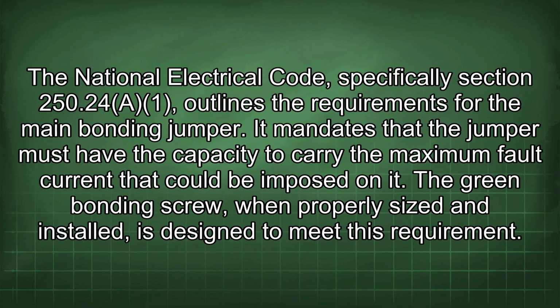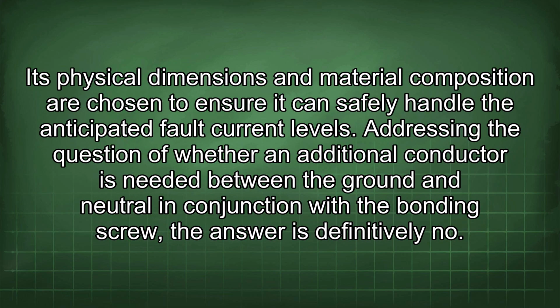The National Electrical Code, specifically Section 250.24(A)(1), outlines the requirements for the main bonding jumper. It mandates that the jumper must have the capacity to carry the maximum fault current that could be imposed on it. The green bonding screw, when properly sized and installed, is designed to meet this requirement. Its physical dimensions and material composition are chosen to ensure it can safely handle the anticipated fault current levels.